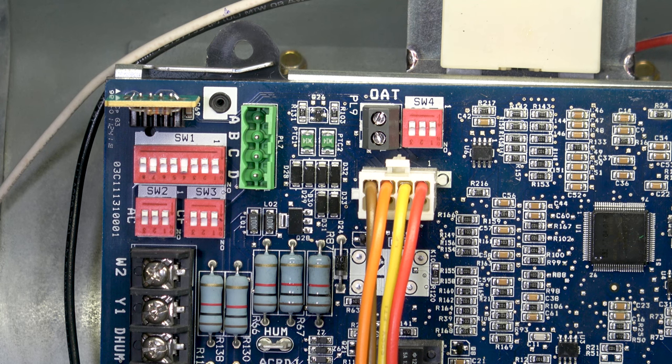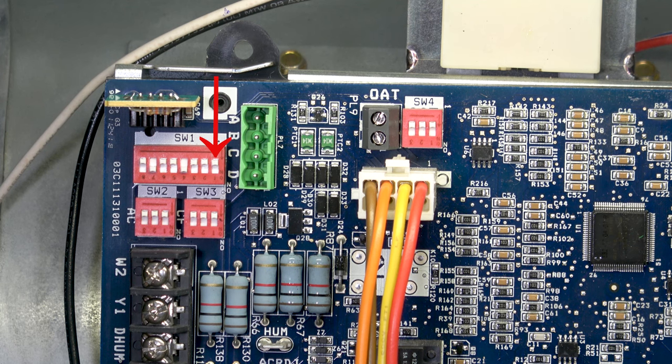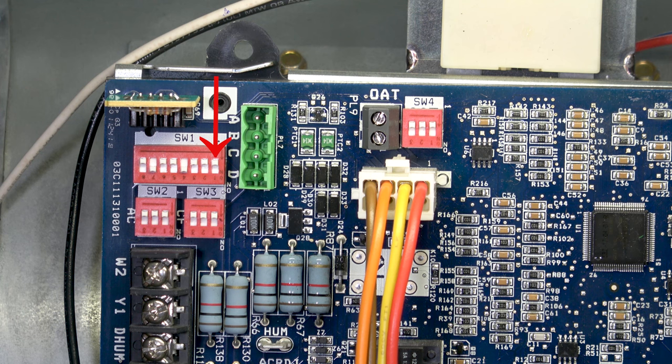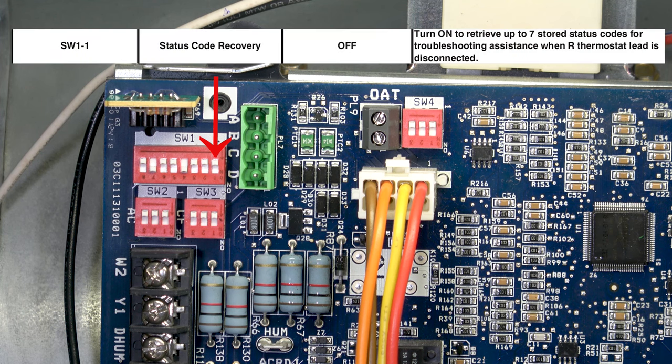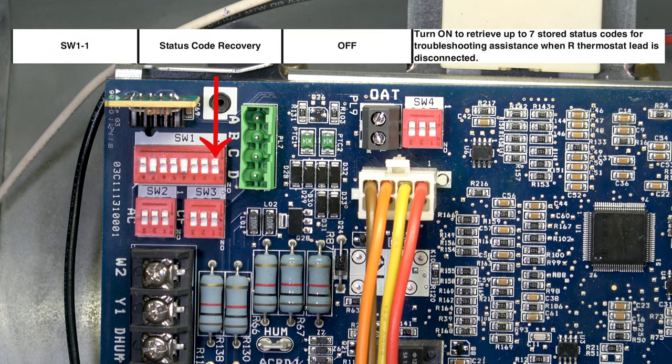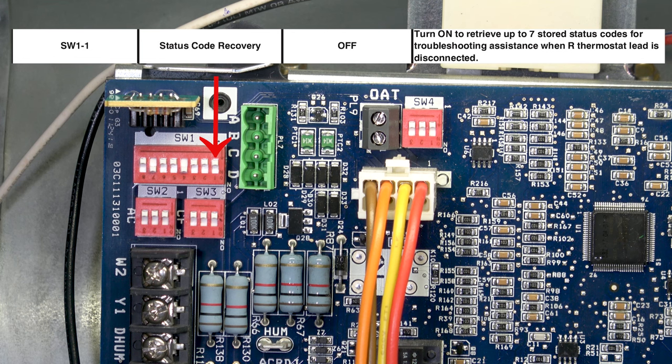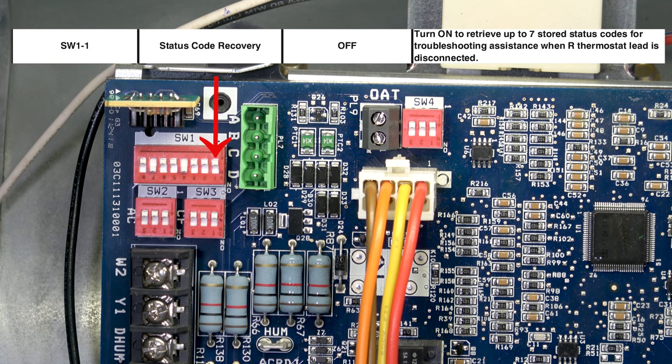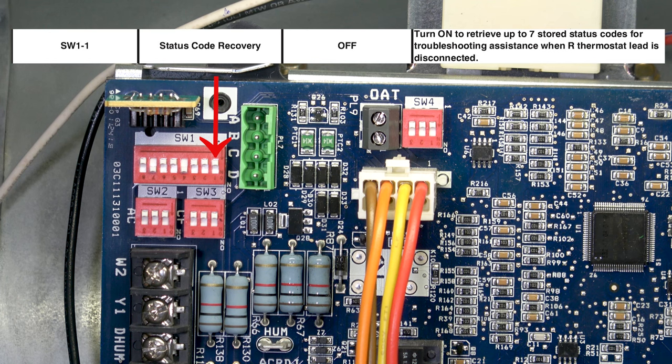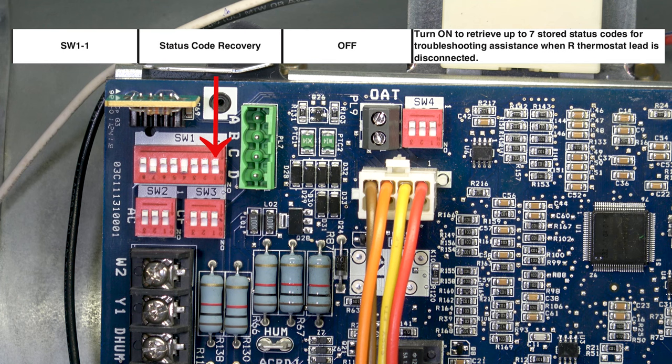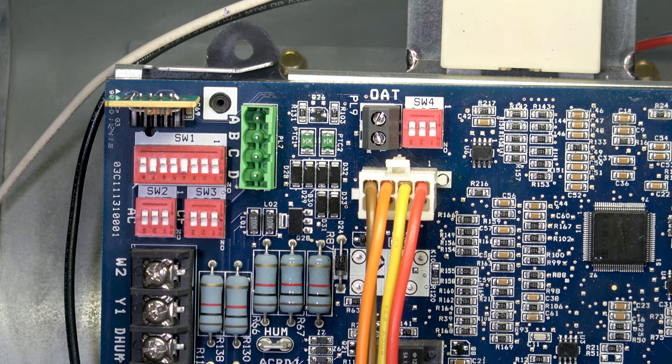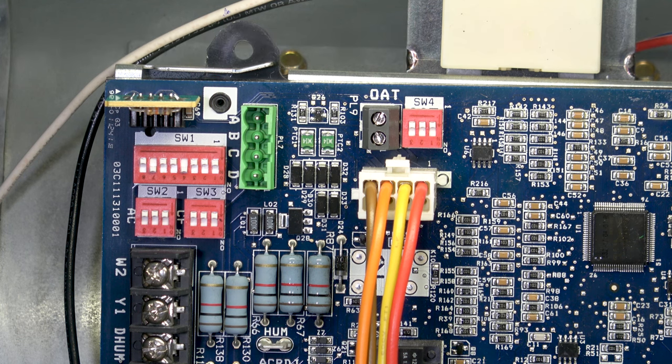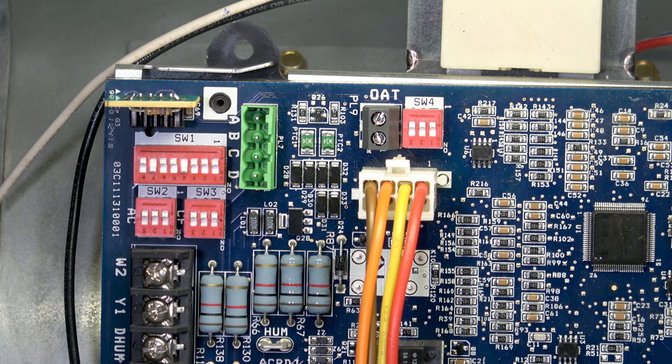SW1 number one is status code recovery. That would be turned on if you wanted to recover any status codes that were happening with the unit. This is strictly a status code recovery switch. That switch has to be off - that is the normal position for operation. Turn it on if you want to recover previous status codes.